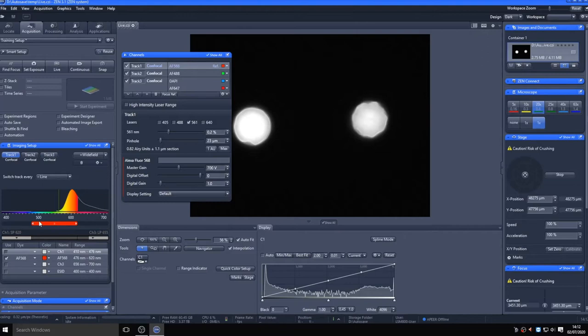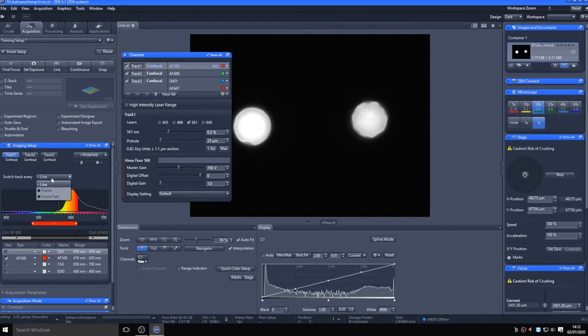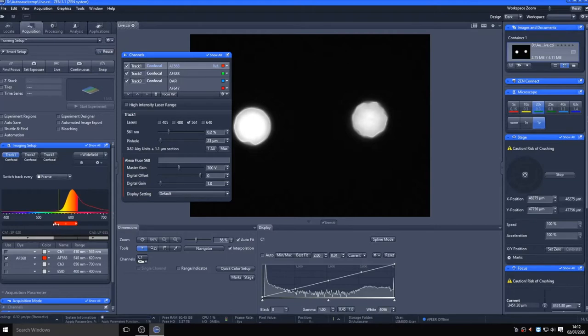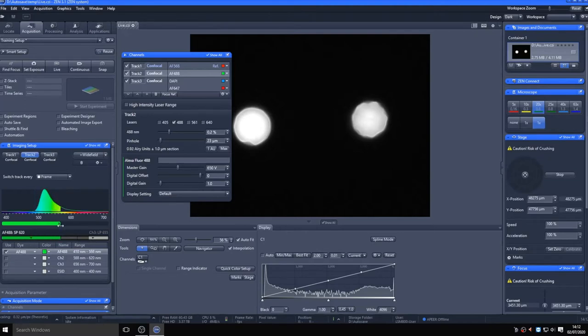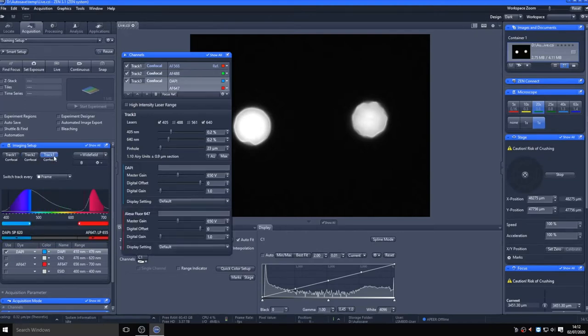If I switch to frame mode, this will allow more specific alterations of dichroic sliders and pinhole diameters and accessory filters on a track-by-track basis, but at the cost of speed of acquisition due to the hardware changes required between tracks. This can be done in the imaging setup tab. If you open up the imaging setup tab, you can see how each track is organized on the sliding dichroic setup, which this microscope is using to direct signal to each of its three detectors.